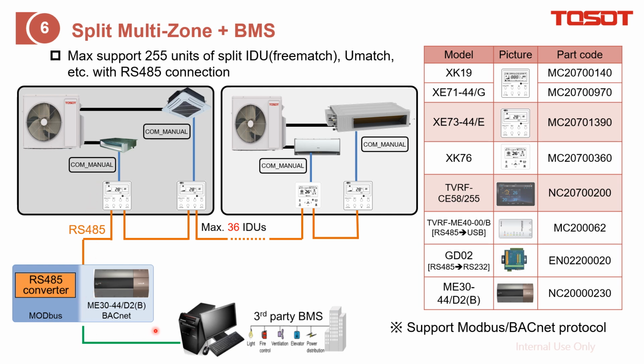If the protocol is BACnet, you need to select this ME30. It can change the signal from Modbus to BACnet for the computer to recognize, which is the third-party BMS. Here I offer you the corresponding wired controller and RS485 converter part codes, and also the BACnet converter, BACnet gateway.